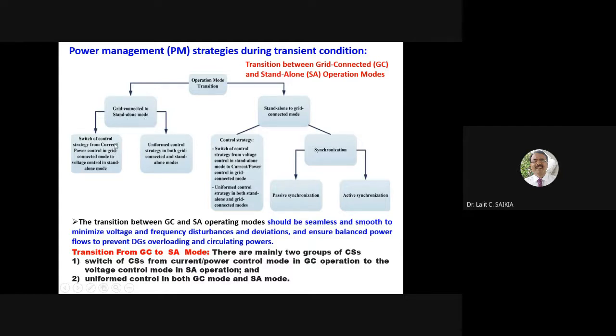Two modes of strategy. One is switch of control strategy from current control or power control in grid connected mode to voltage control in islanded mode. So this is one. That is, switch of control strategy from current control or power control mode, which is there in the grid connected mode, to voltage control in islanded mode or standalone mode. So this is the first one.